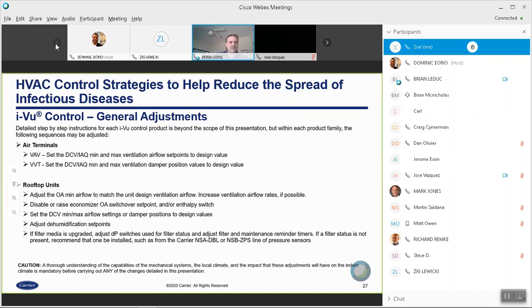Filter media, again, this is a great concern. If they choose to increase the filter media, you'll need to adjust the DP switch settings, assuming you're doing it with a switch-based sensor. It's an analog. You'll maybe have a set point in your logic to adjust. If filter statuses are not present, we do recommend that they be installed, or you can recommend to your customer that they be installed.